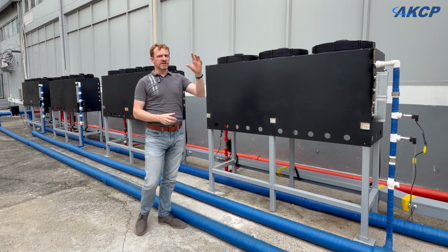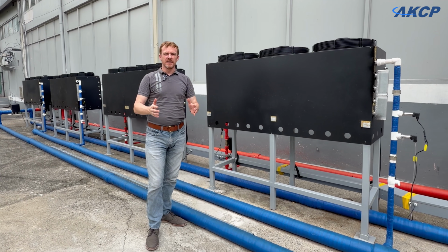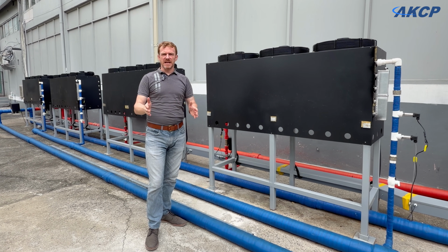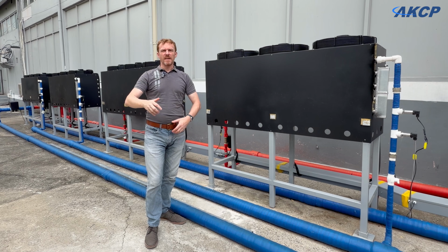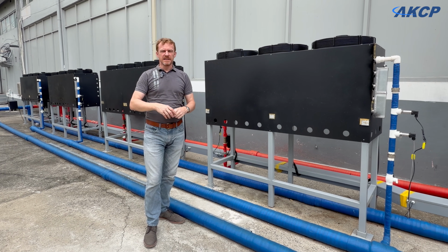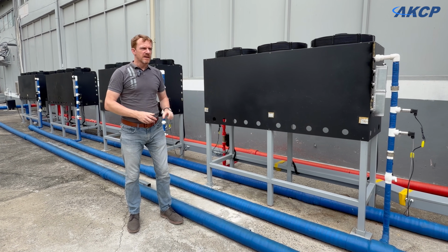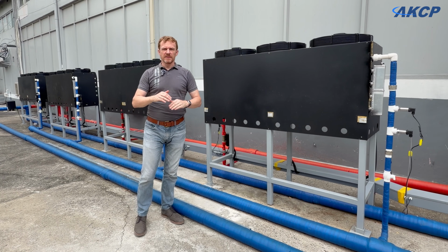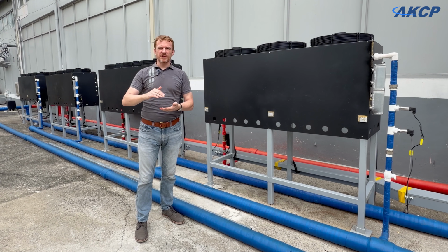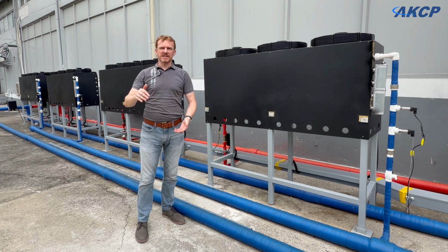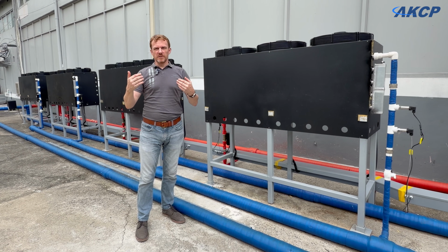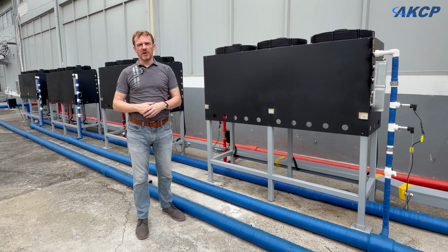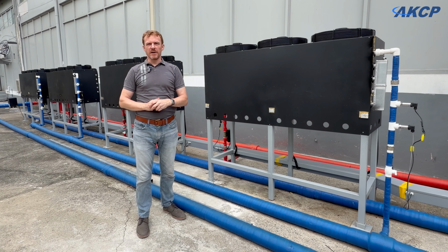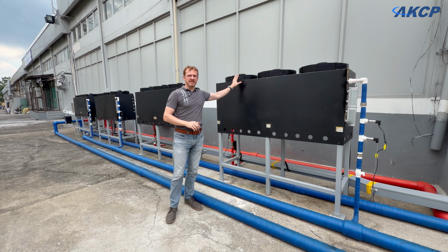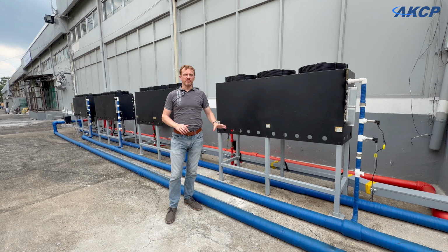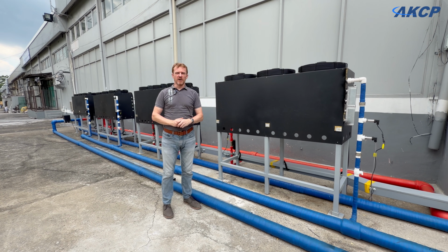So the chiller's job is basically to maintain the thermal mass at a specific temperature. So we have a tank of water and the chiller wants to maintain that at, say, 22, 23 degrees. The warmer the water we send back, the quicker the water temperature in that tank rises, and the faster it rises, the sooner we have to turn on the compressor of the chiller. So if we can drop the temperature of the water here, it reduces the amount of load that we have to put onto the chiller.